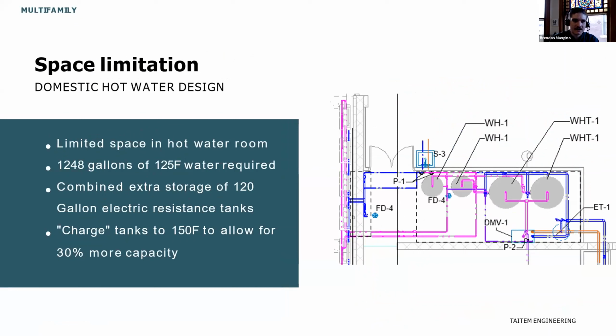The second design challenge we ran into is space limitation. So this right here, this is the domestic hot water room. As you can see, there's not a lot of space. We have 2 500-gallon tanks and 2 120-gallon tanks that take up most of the space in there. So the way we tried to address the space limitation is that we actually combined 2 different systems. The backup electric resistance is housed within the 120-gallon storage tanks that we need to increase the effective storage of our system.